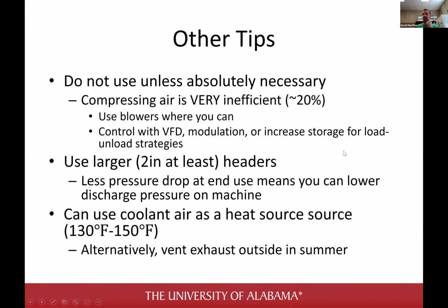Other tips I have for anyone about compressed air. It's a very involved subject, and again, this is a whole section of my class, but another tip I have is don't use compressed air unless it's absolutely necessary. I was telling you that getting the electricity from that compressor cabinet to being compressed air in the end is only about 20% efficient. The rest is going to waste heat. So if you can use a blower instead of compressed air, do it. Let's just say you have a bag house for dust collectors. If you can use a blower somehow instead of pulsing with compressed air, please do it. The savings are immense, any place that you can do that. Air knives, for example. You can get away with using a blower instead, please do.